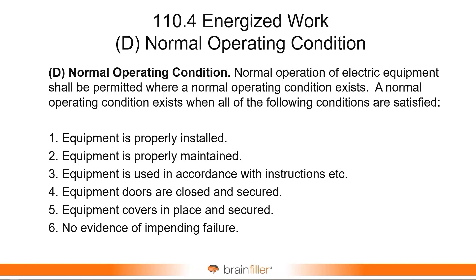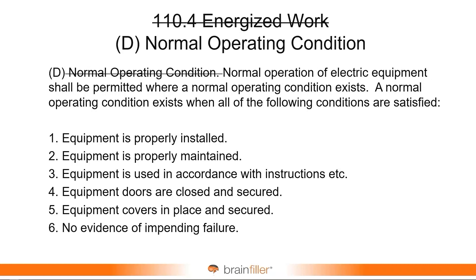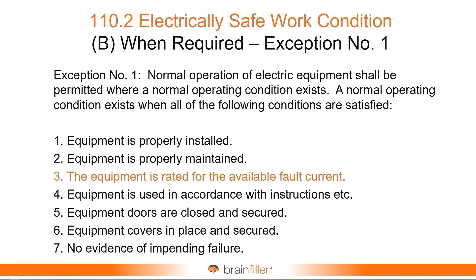If you're just going to operate the equipment, let's have a checklist. If you can check all six boxes, then go ahead and operate the equipment — that is what it is designed for. Now there are some changes to it. This is part of 110.2 electrically safe work condition B, when required, exception number one. The new addition was that the equipment is rated for the available fault current.